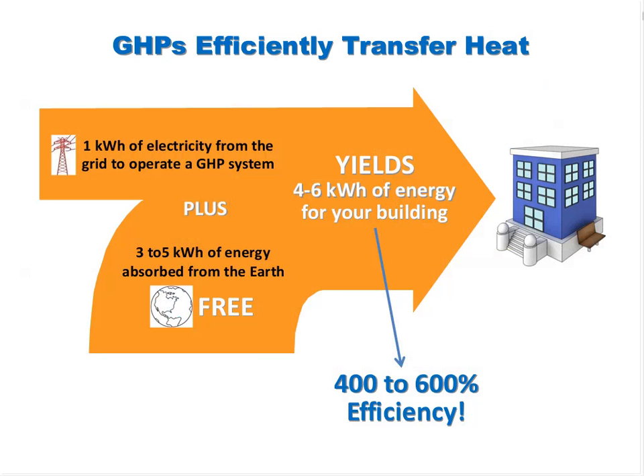Geothermal heat pump systems do use electricity, a little bit. They've got to run the pumps and the compressor and so forth in order to tap the heat from the ground. But for every kilowatt of electricity we use in a GHP system, we pull 3 to 5 kilowatts of energy from the earth. That yields 4 to 6 kilowatts of energy for the building, which totals up to 400 to 600% efficiency. And that's our true selling point, the efficiency, and not only that, but the comfort, and there are other aspects of heat pump use that are very favorable for buildings and their occupants.